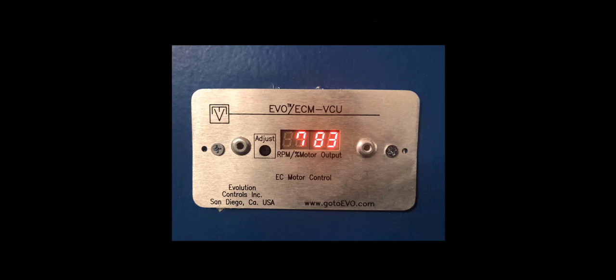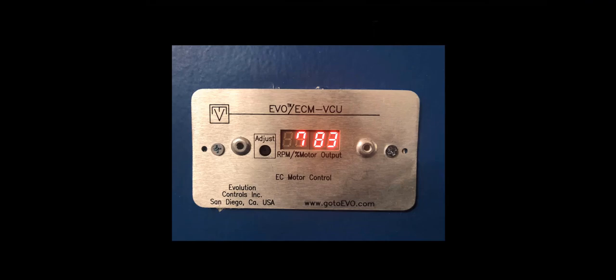The second type of control for the EC units is the remote mount control option. These units are supplied with an on/off switch installed on the control box and a wall mounted speed controller which has a potentiometer for adjusting airflow setting and a digital display that indicates the unit flow index so you can monitor airflow. The control box and wall controller is supplied with quarter inch spade terminals for field connection. A single controller can be wired to up to five units. However, in this configuration there is no network functionality provided.